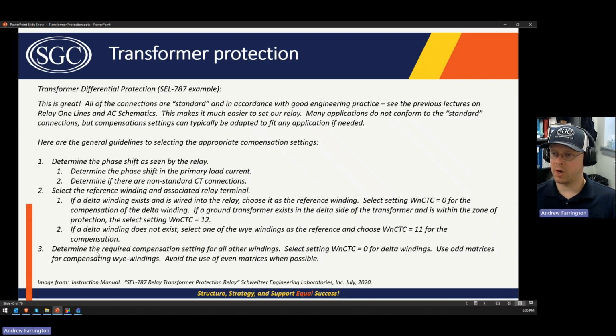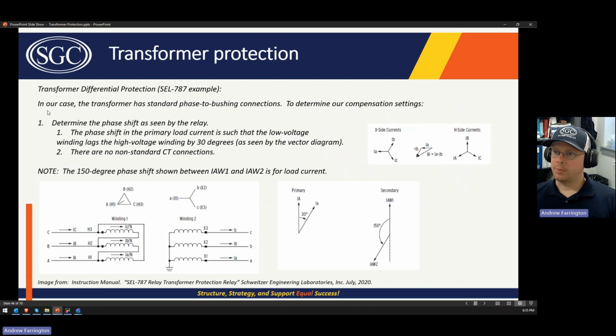And then step 3 is to determine the required compensation settings for all other windings. So select setting 0 for delta windings, use odd matrices for compensating Y windings, avoid the use of even matrices when possible, which is what I just said. All right, so in our case, the transformer has standard phase to bushing connections, and to determine our compensation settings, we look at the phase shift as seen by the relay. The phase shift in the primary load current is such that the low voltage winding lags the high voltage winding by 30 degrees, as we can see by looking at the vector diagram, and there are no non-standard CT connections.